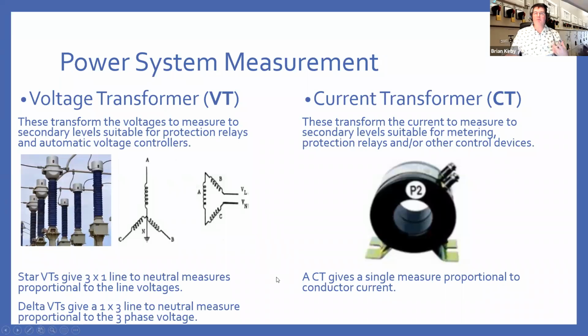Finally, you need to be able to measure what's going on in order to have any idea of what actions are needed. So voltage transformers, the most common arrangement is the 3-phase to neutral voltage arrangement, as shown here. But sometimes if you have, say, a delta transformer, you may want what's called a broken delta VT, which will then give you a neutral displacement measurement as well as the 3-phase voltages. Current transformers will be 1 per phase, and you will be monitoring the current flowing in each line.